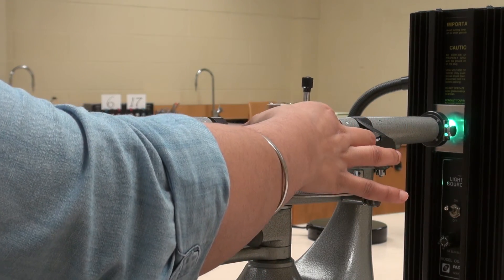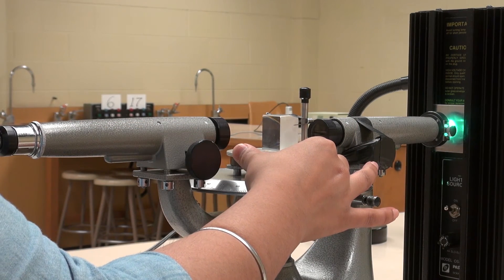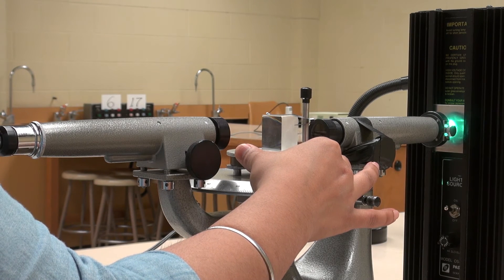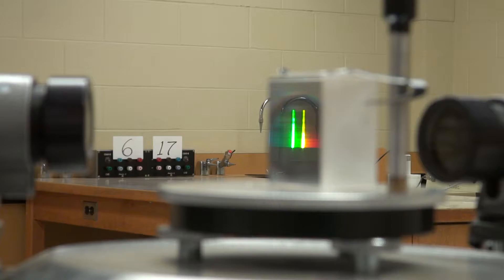Now place the prism on the spectrometer table so that the light passes through the prism. Ensure that the frosted side of the prism is against the post of the prism table.